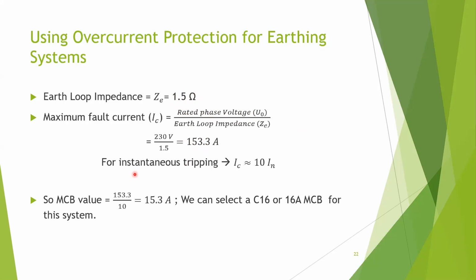And so, you will understand this later. MCBs have instantaneous tripping curves. Instantaneous tripping is activated at around 10 times the IN. IN is the rated current. So if it is a 10 ampere breaker, it will trip instantaneously if the current through the breaker is 100 amps. So we can use that to design the tripping characteristics of a TNC system. So we are going to learn these things, so don't worry.